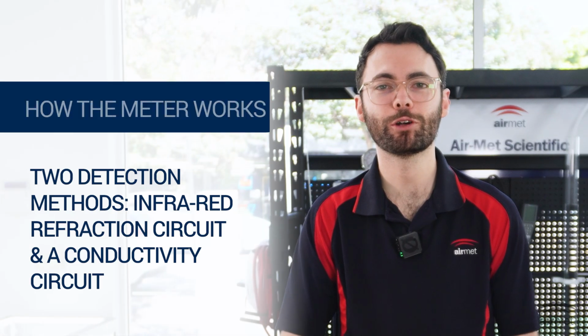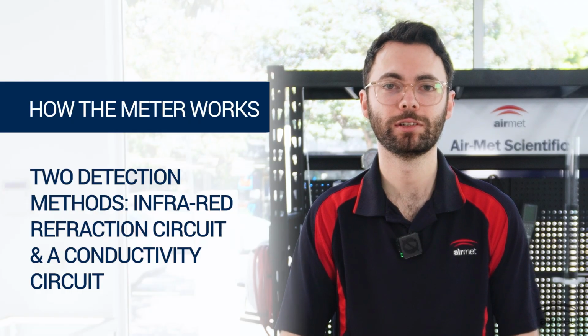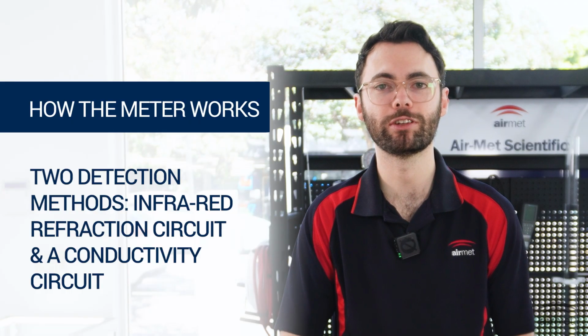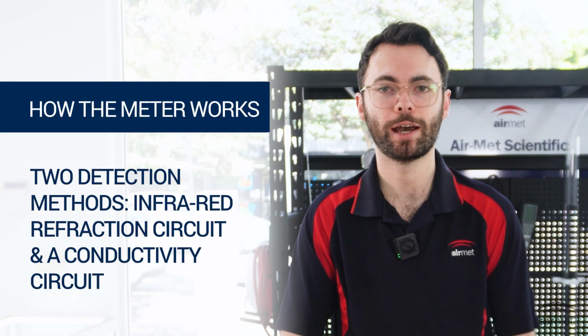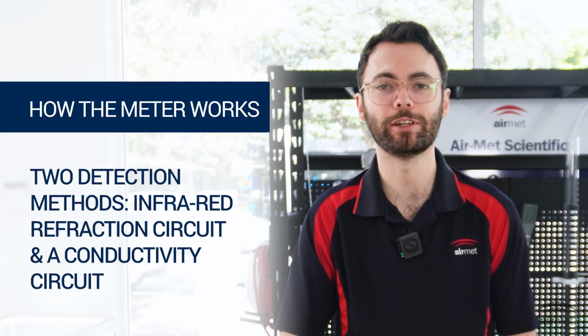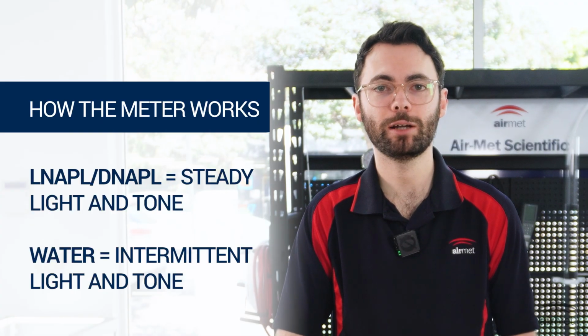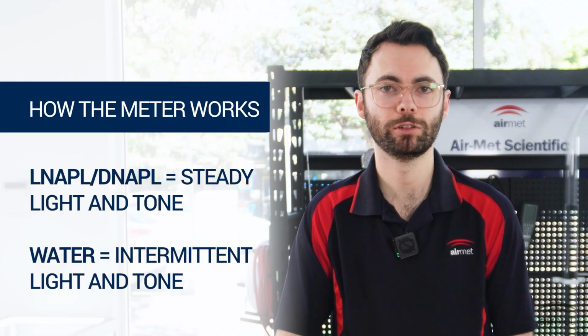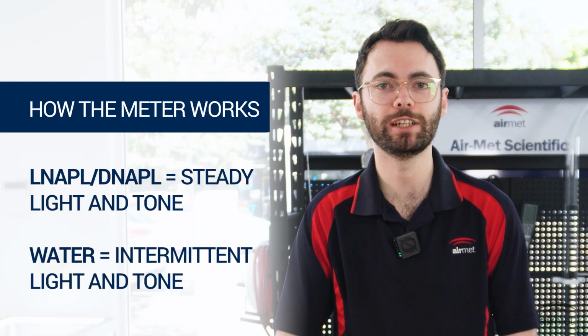The interface meter probe combines 2 detection methods: an infrared refraction circuit which detects when the probe enters a liquid, and a conductivity circuit which distinguishes between water and product. Product detection of LNAPL and DNAPL will show a steady light and tone, whereas water, which is conductive, will have an intermittent light and tone.